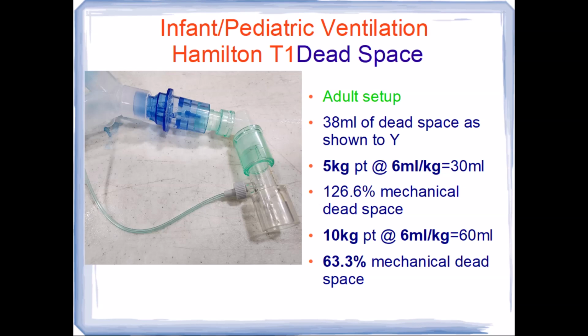So if we set the weight of the patient and the ventilator defaults to the 6 milliliters per kilo, that's going to be a 30 ml tidal volume for a 5 kilo patient. Well, we have 38 mLs of dead space utilizing this setup. That's 126.6% mechanical dead space. So all we're doing is we're constantly rebreathing the exhaled CO2.